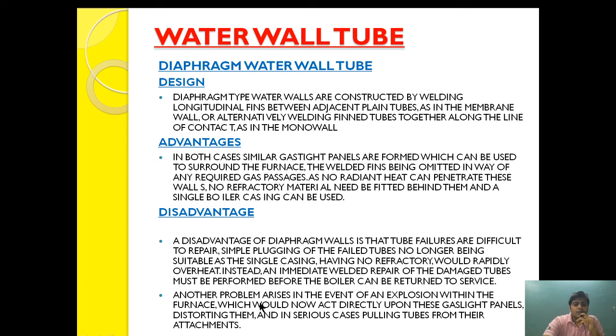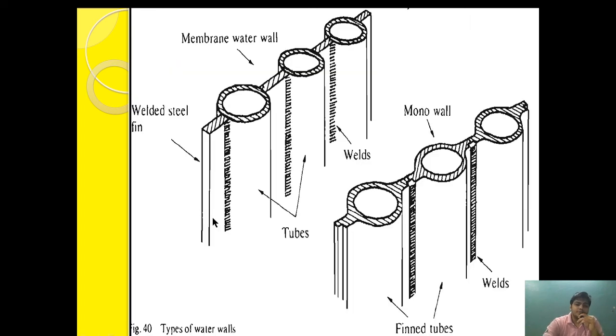Another problem arises in the event of an explosion within the furnace, which would act directly upon the gas-tight panels, distorting them and in serious cases pulling out the tubes from the attachment. If the tubes are pulled out of the attachment, complete damage results and the whole membrane wall tube needs to be replaced.